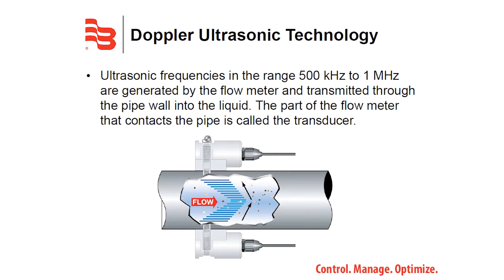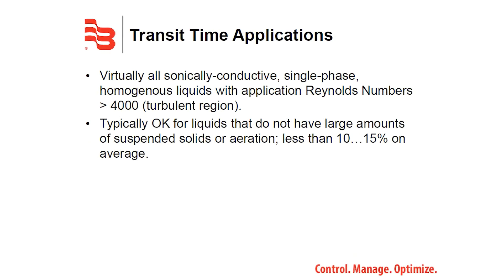Ultrasonic frequencies in the range of 500 kilohertz to one megahertz are generated by the flow meter and transmitted through the pipe wall into the liquid. The part of the flow meter that contacts the pipe is referred to as the transducer. Applications for transit time flow technology are virtually all sonically conductive, single-phase, homogeneous liquids.